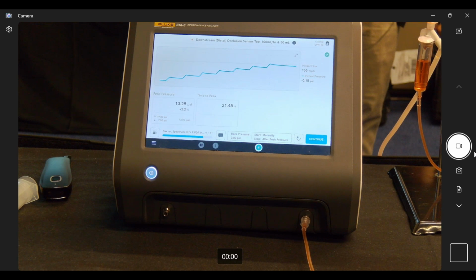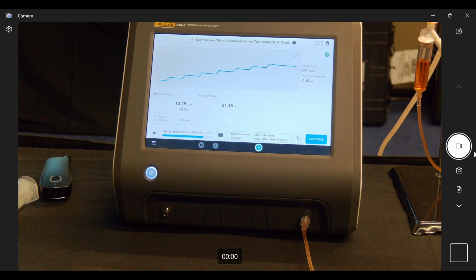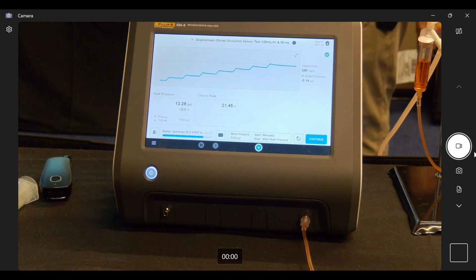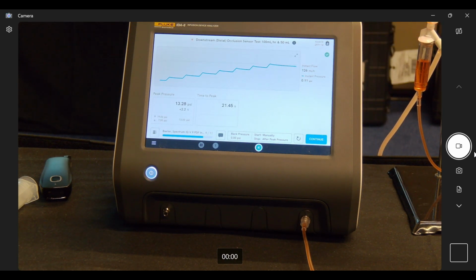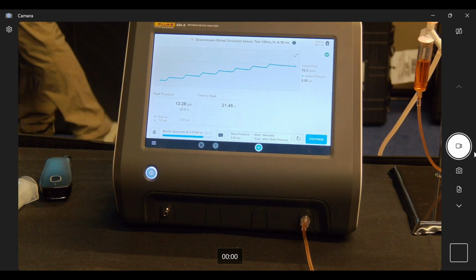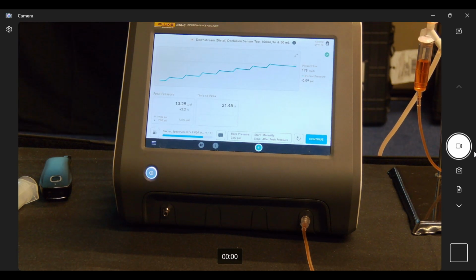If you do statistical analysis, when you actually start to capture this, you can start to do trending over time. Nuvolo has the capability - if I took this actual peak pressure (by the way, I'm not staring at this, and my pressure hasn't backed down - 13.28 PSI), I could now run all 5,000 of my IV pumps. If I put those exact figures into it, I can go into Nuvolo and use some figuring, and grab all those data points and say, what was my average peak pressure this year?